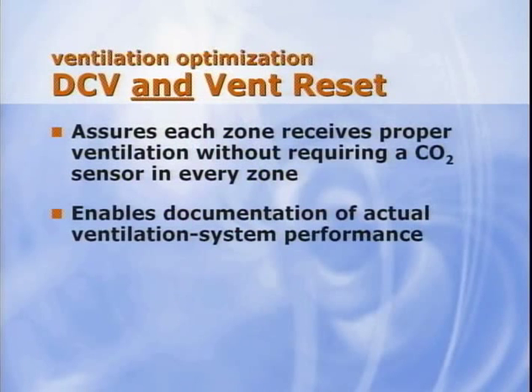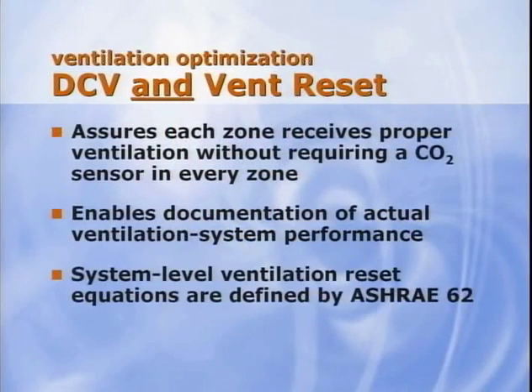Next, it enables documentation of actual ventilation system performance. The VAV controller for each zone communicates the ventilation airflow for every zone to the BAS, even for those zones that do not have a CO2 sensor. So you can generate reports showing ventilation CFM in every zone for every hour. Finally, the system-level ventilation reset equations are explicitly defined in an industry-wide standard, ASHRAE 62. So they're defendable. Team, thanks for taking us through those system-level controls.